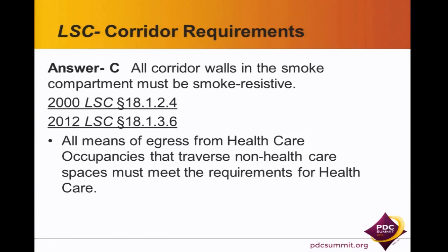You know, this is one that makes a lot of sense if I'm moving horizontally into the other occupancy that I need to meet the healthcare requirements. But folks, if I've already moved those patients downstairs, I don't know if I need an 8-foot corridor from that point on. But that's what the code says. I have to meet the healthcare requirements if I'm egressing through that space.